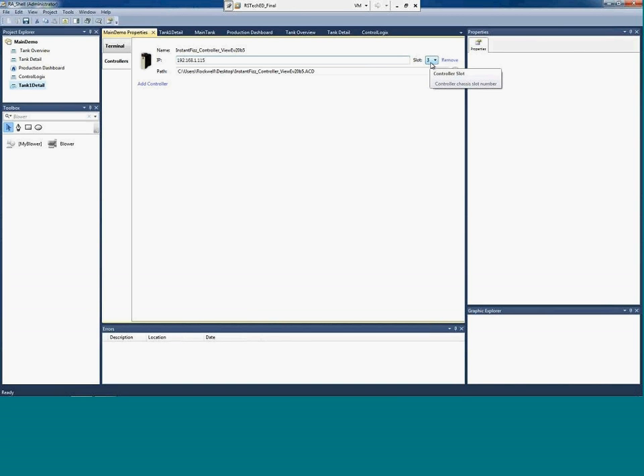But the mechanism that you'll be able to demo with the View Designer will be a lot easier, because we've taken the command capability that we have in View SE today, and we've brought that right down to the PanelView level of product. And let me show you what I mean by that. I've got the pump selected, I've got my Events tab selected, and you can see that I've defined a touch event for the pump. And I've associated a toggle command with that touch event, so that each time the pump is pushed, we will toggle the Tank Master pump control and effectively start and stop the pump.